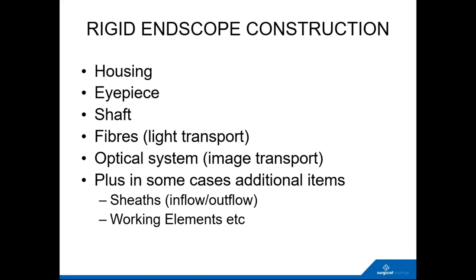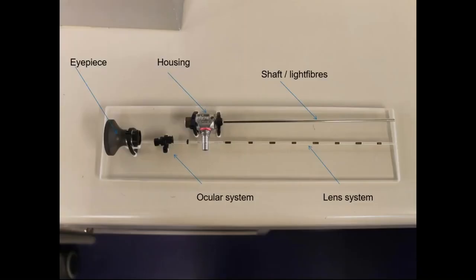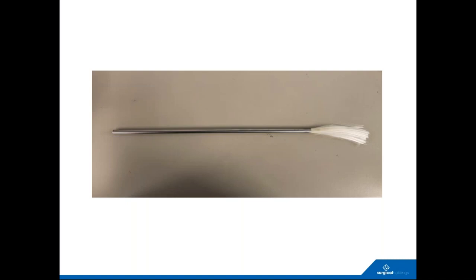There's a variety of parts to it, but it's probably best if I actually just show you a broken down instrument. This is a very simple, small diameter, broken down endoscope. On the left, you can see the eyepiece, then moving right, there's the ocular system that integrates with the eyepiece. The housing, you can see this post there is where the light guide cable connects and takes light down the shaft using fiber optics to the tip of the instrument, and then the lens system returns the optical image through and back to the eyepiece. There is, as I say, fibers. Many people forget there are fibers within a rigid instrument, and that's just an illustration of that.